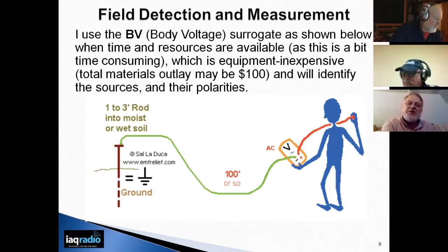Using this arrangement, where you use a ground rod and a long wire to your meter, you can identify which circuits are involved. The meter can be any number of types. I use something like this, where I have a dongle that I attach and simply contact the metal, which is part of the input. The other input is the reference wire on this corner, which is the ground wire going outdoors. I hesitate to use a ground lug on an outlet, because there's a good chance the wire may not be connected, or it could be miswired so that you have 120 volts live on that ground lug. I hesitate very much to use that as a measuring reference.